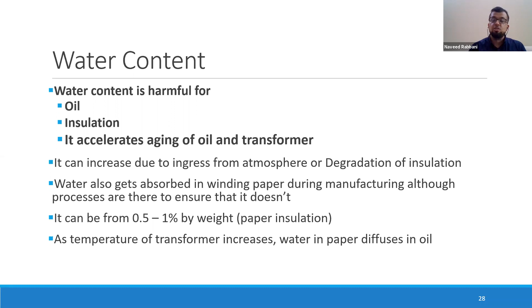Furthermore, during manufacturing, a substantial amount of water is absorbed in transformer windings, 0.5 to 1% in some cases by weight of paper insulation. So that water is also present in the paper insulation, and when the transformer heats up and thermal equilibrium is achieved, the water present in the paper insulation diffuses into the oil. So water retained in paper insulation during manufacturing is also a source of water content in transformer oil. It's important to keep a check on it, and if it starts to increase, you should identify the root cause and source of this water increase, because it's very damaging for the overall electrical asset.